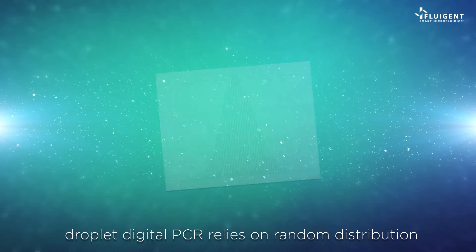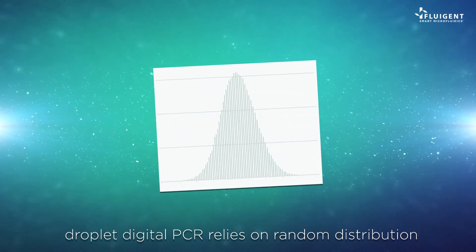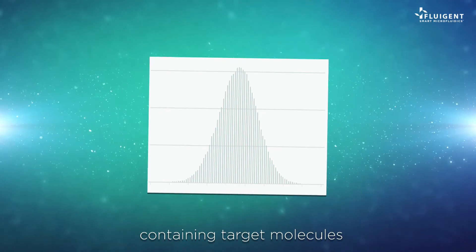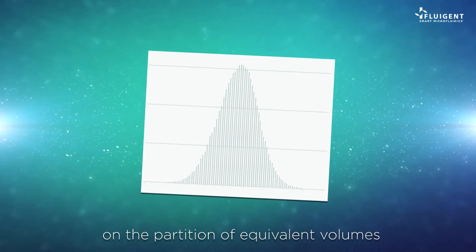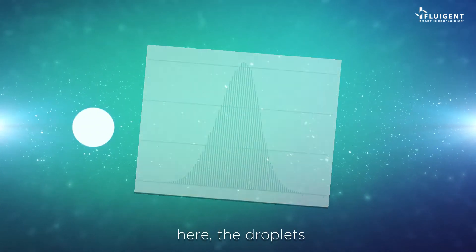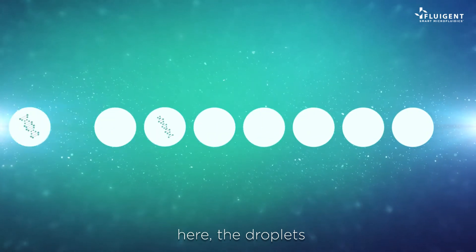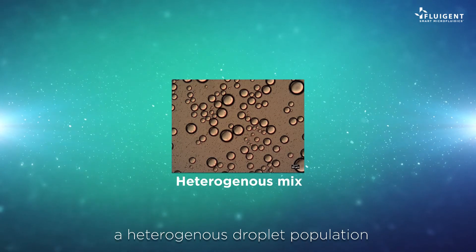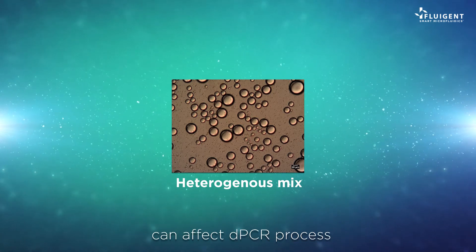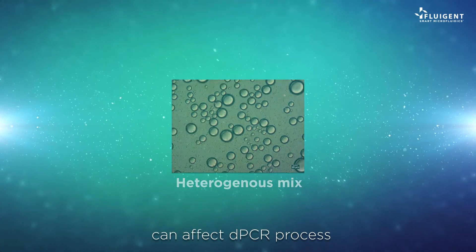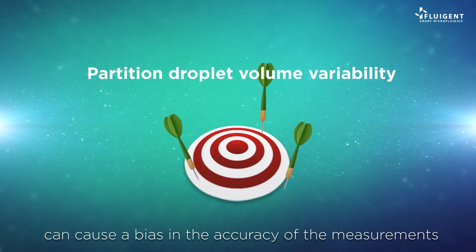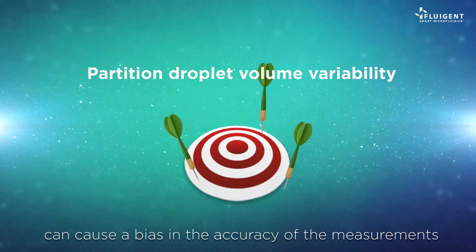Droplet digital PCR relies on random distribution of dPCR mix containing target molecules on the partition of equivalent volumes. Here, the droplets must be uniform. As a consequence, a heterogeneous droplet population can affect the dPCR process, and demonstrations show that partition droplet volume variability can cause a bias on the accuracy of the measurements.